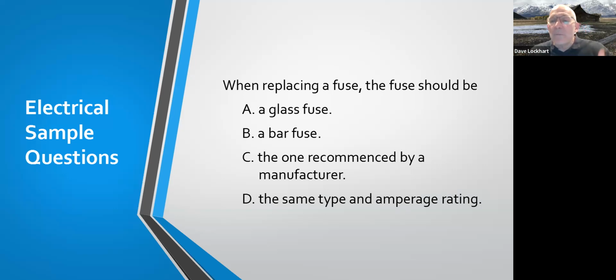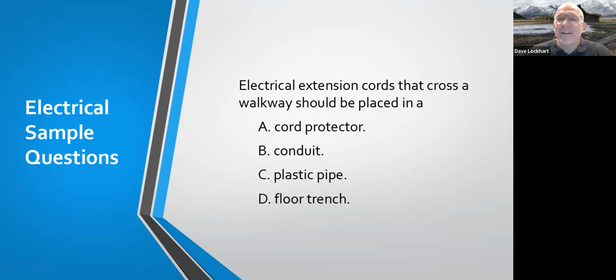Because again, if you're putting in the same type that was there and it still blows, then you can really troubleshoot the system, find out what's wrong, and then maybe go to the manufacturer's recommendation beyond that. Because finding the manufacturer's recommendation may take more time to go through and research and get that. You may not have that. So definitely replace it with the same type and amperage rating that you have. Definitely want to do that, and not, as a lot of people may do, go try to find a higher amperage. You know, it's inconvenient because of, well, I don't have to get into that stuff, but you guys are qualified technicians out there.